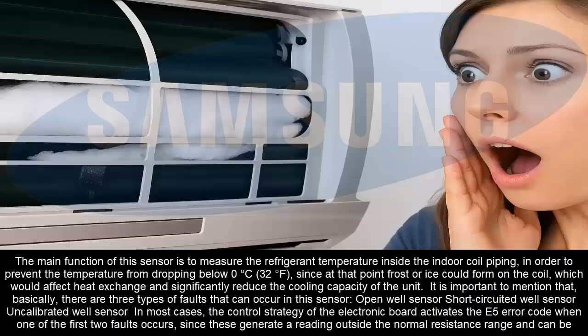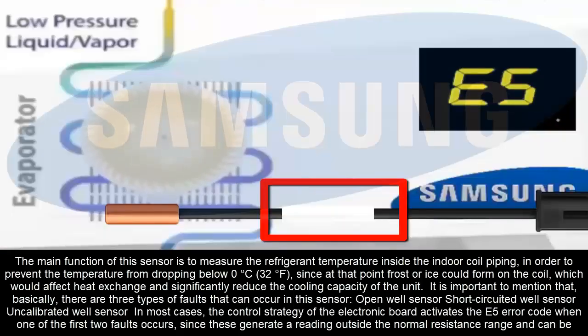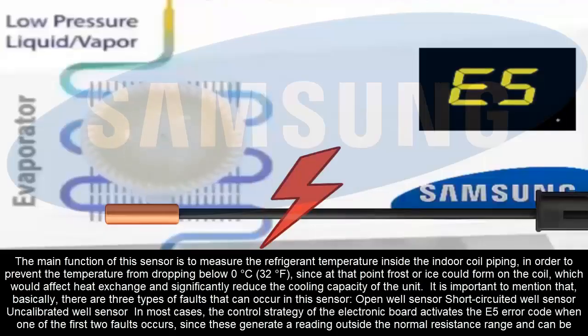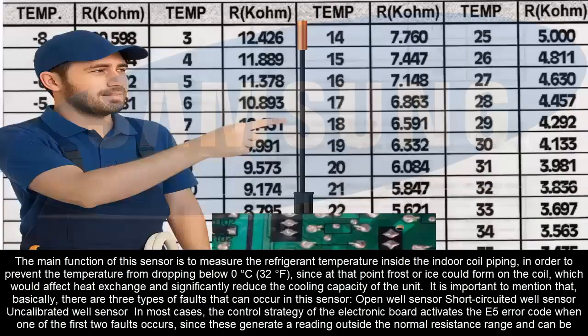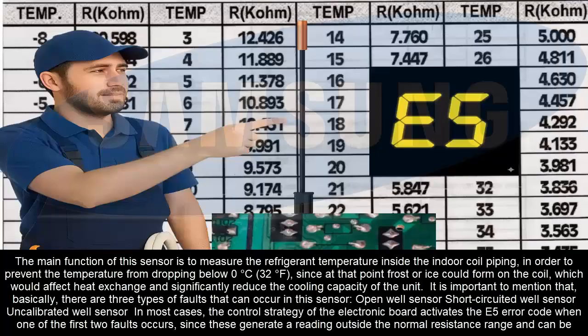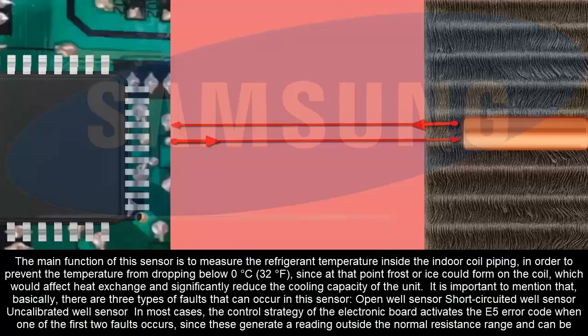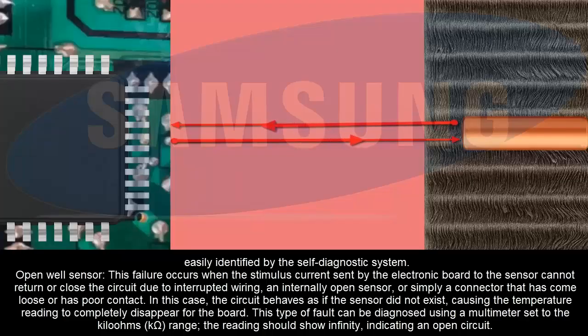It is important to mention that, basically, there are three types of faults that can occur in this sensor: open well sensor, short-circuited well sensor, uncalibrated well sensor. In most cases, the control strategy of the electronic board activates the E5 error code when one of the first two faults occurs, since these generate a reading outside the normal resistance range and can be easily identified by the self-diagnostic system.